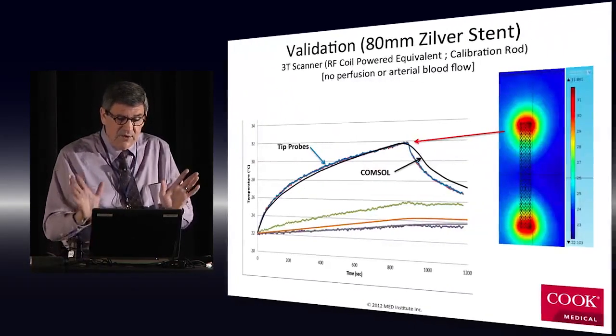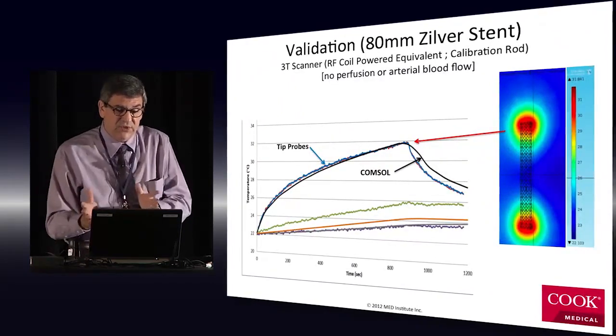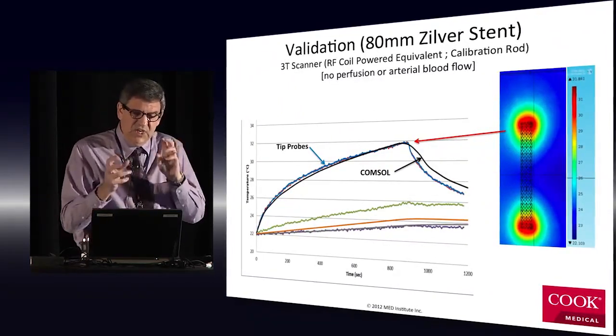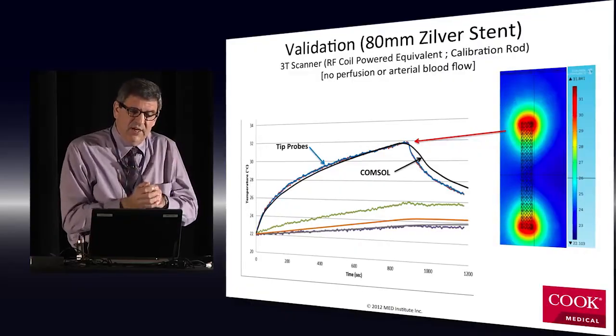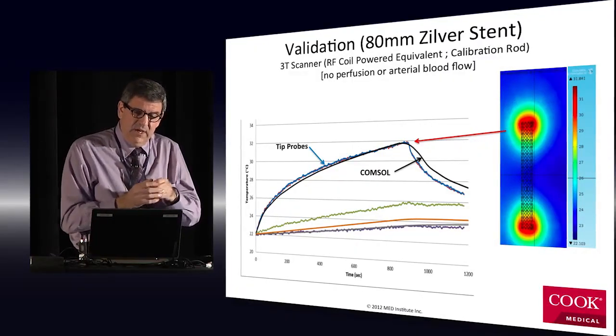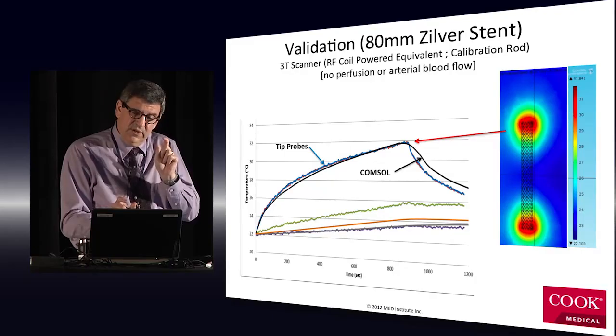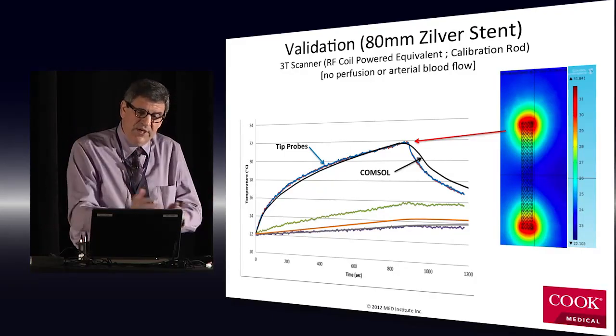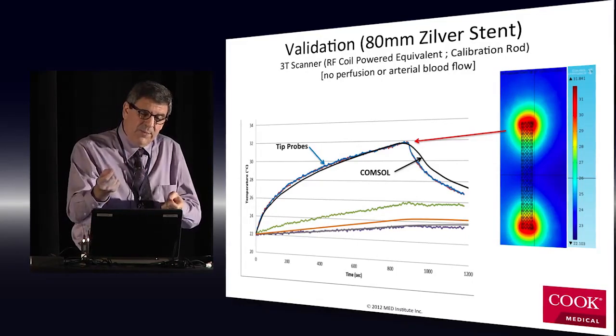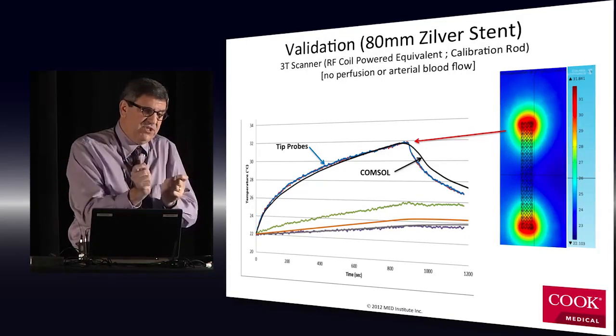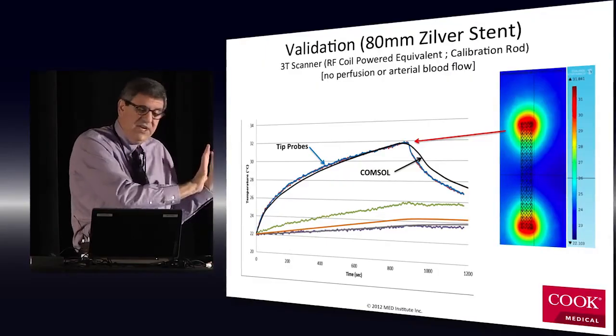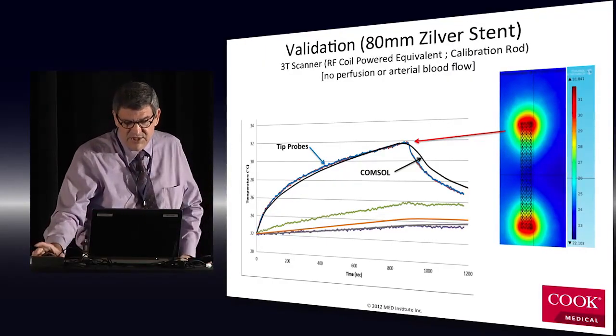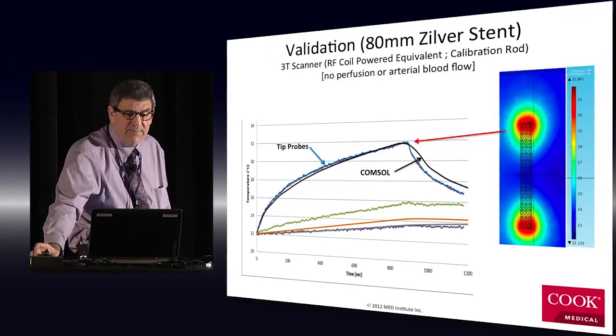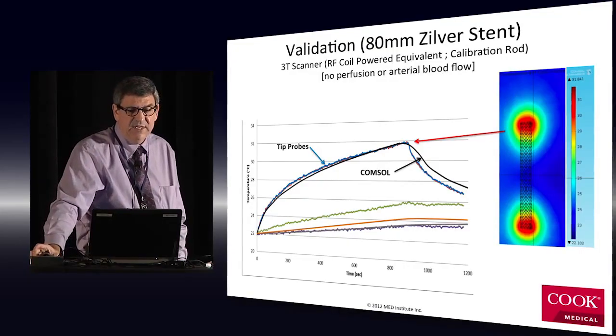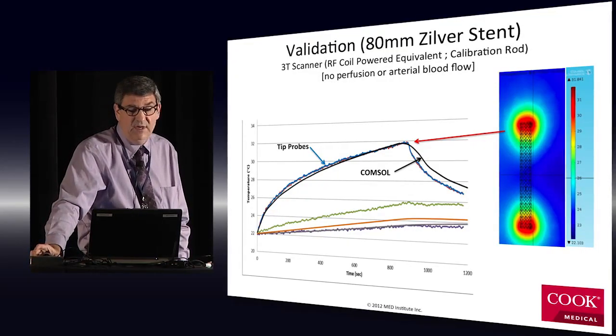Kind of one of the money slides is we then go back to the Zilver stent, which I showed you, which is this intricately designed, laser cut, nickel titanium, 10 millimeter diameter, 80 millimeters long, and we put it into the 3 Tesla scanner, and we put the thermocouples at the end. Now we use the voltage that we derive from the calibration rod. We don't change it. We power it on. This is a 900 second or 15-minute test, and bang, we hit the maximum temperature within a couple tenths of a degree.